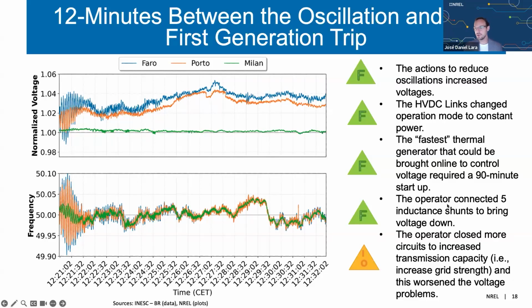In this process, under these 12 minutes, the operator connected 5 inductance shunts to try to bring the voltage down. They closed and opened circuits. If you go through the report, there's several pages of all of these maneuvers the operator was taking to try to control the voltage that was already rising. So again, the interesting phenomenon here is that after the oscillations happen, it stands to reason that some of the protocols the operator followed to control the oscillation were just creating voltage runaway problems. And the operator closed more circuits to try to control the oscillation, which is kind of what you learn in your power systems class. The oscillations are created by a weak grid, so you close more circuits, you create this grid strength, but it just worsens your voltage rising problems.